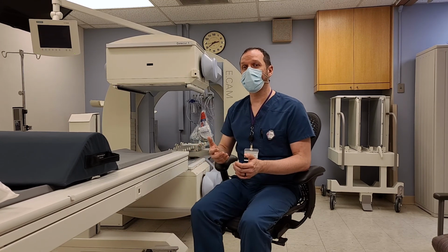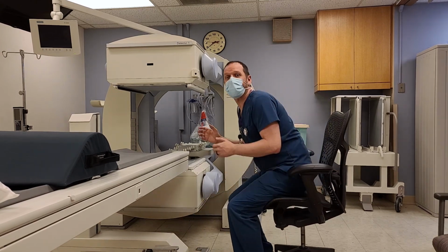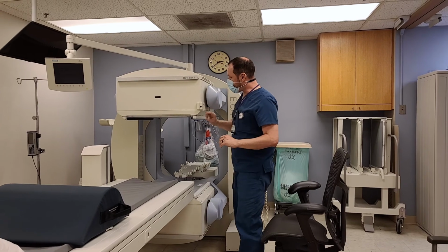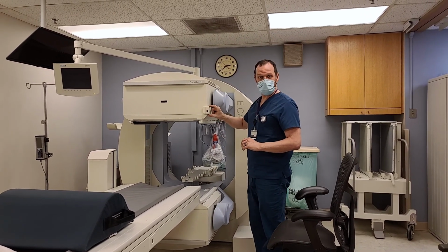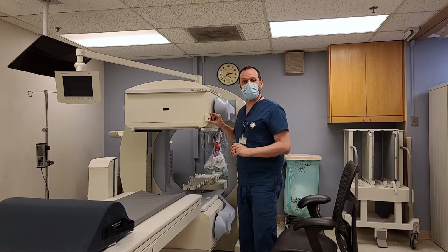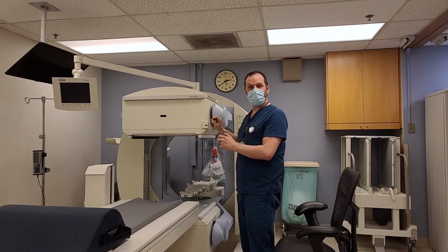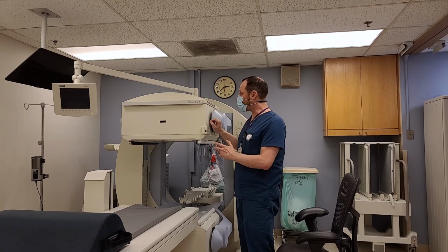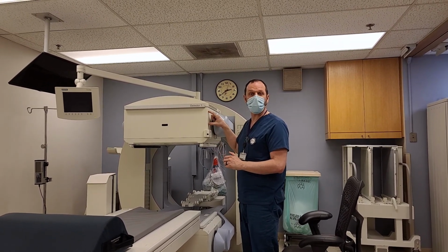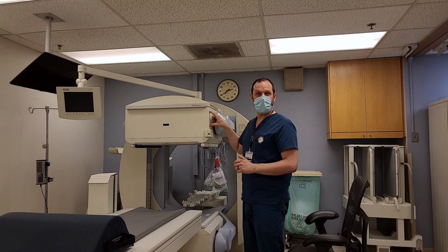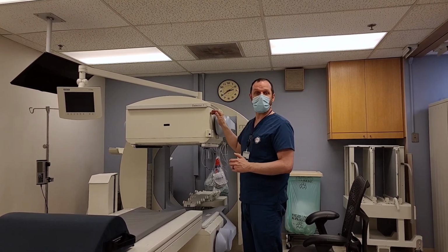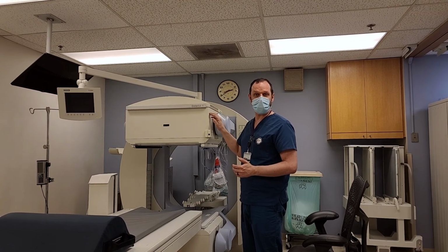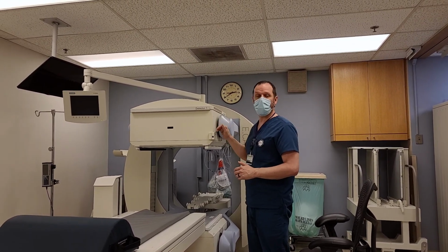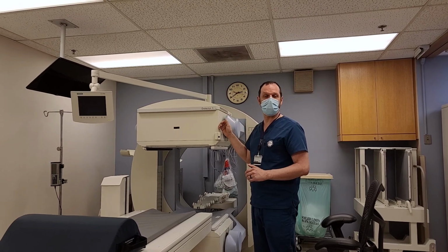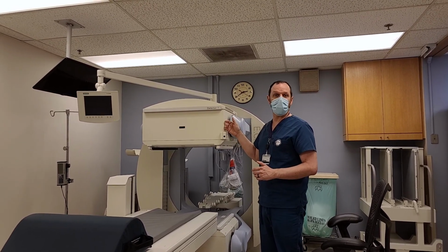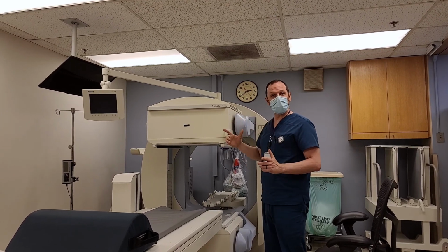Now, inside this machine, the way that that works is inside of here there is a crystal. The crystal lives about at this level. That crystal, when it gets hit with a radioactive ray, will then turn that radiation into a light beam. The light beam goes up into this part where there are things called photomultiplier tubes. The photomultiplier tubes increase the light, and then they send that back onto something that detects that and turns it into an electrical signal. The electrical signal, dependent upon what photomultiplier tube it was hit and where it was hit, will then calculate the origin of that radiation ray and will give us a 2D image.